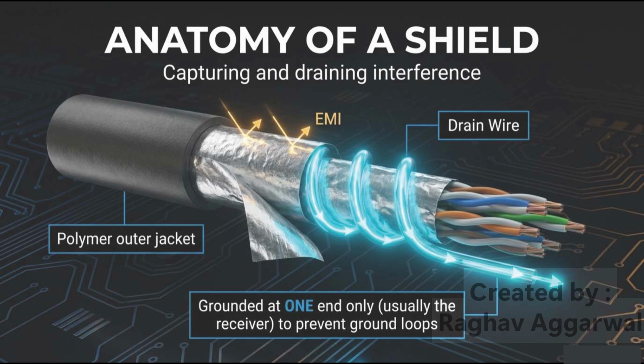The key function of the shield is to collect external electrical noise and safely channel it away from the signal conductors. In industrial environments filled with motors, power cables, and switching equipment, shielding helps ensure that instrumentation data remains accurate and dependable. Accurate measurements lead to better control decisions, safer operations, and improved process performance.